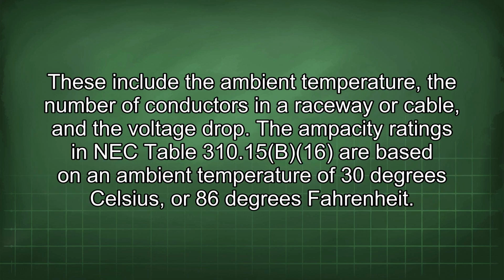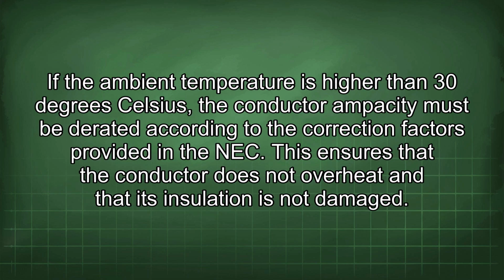These include the ambient temperature, the number of conductors in a raceway or cable, and the voltage drop. The ampacity ratings in NEC Table 310.15(B)(16) are based on an ambient temperature of 30 degrees Celsius, or 86 degrees Fahrenheit. If the ambient temperature is higher than 30 degrees Celsius, the conductor ampacity must be derated according to the correction factors provided in the NEC. This ensures that the conductor does not overheat and that its insulation is not damaged.